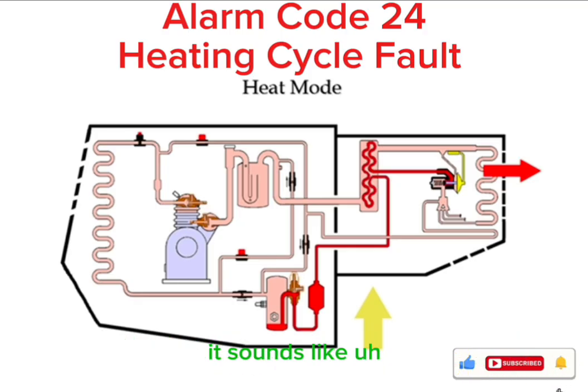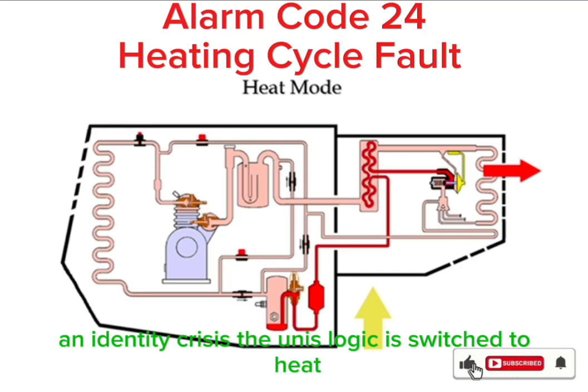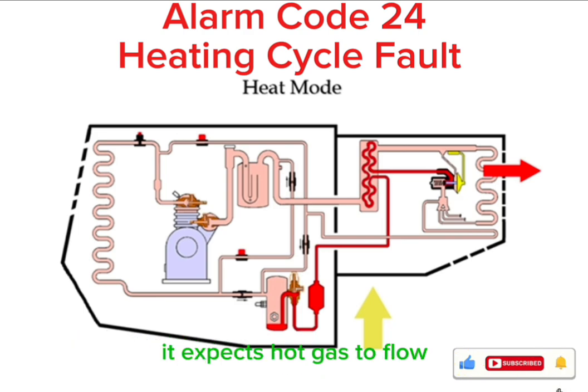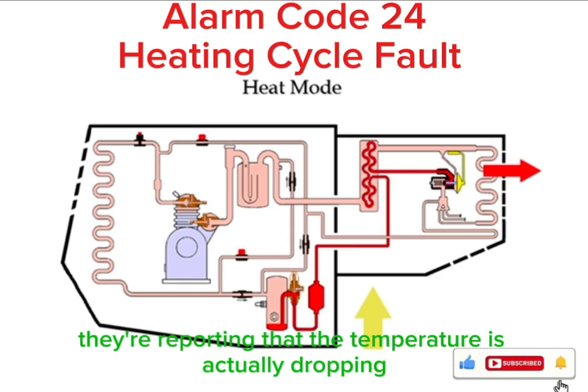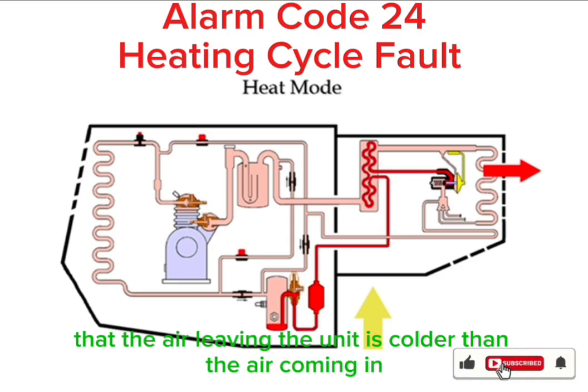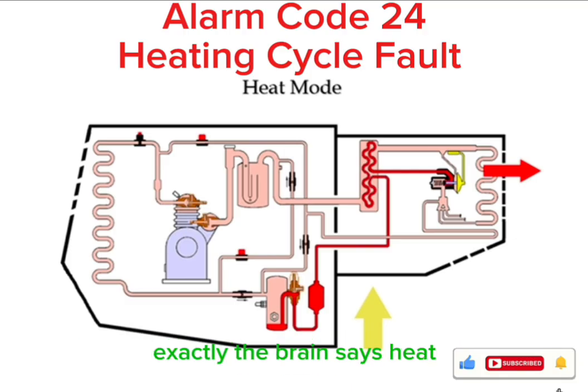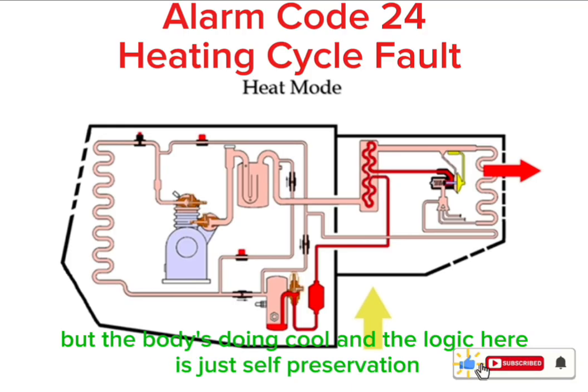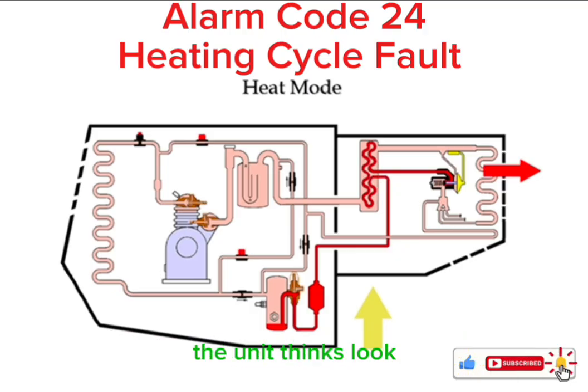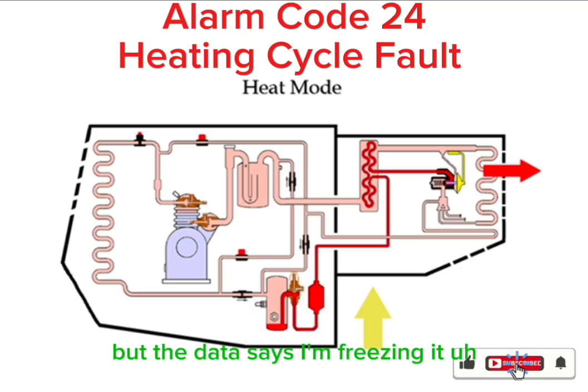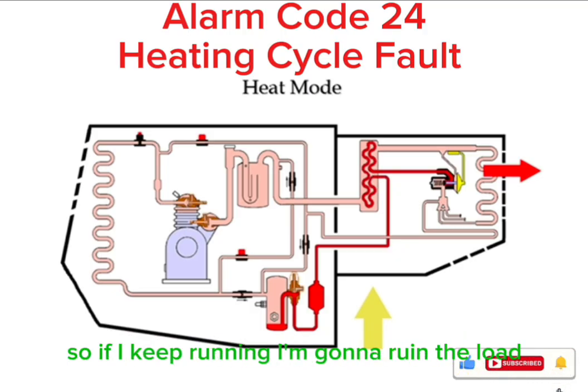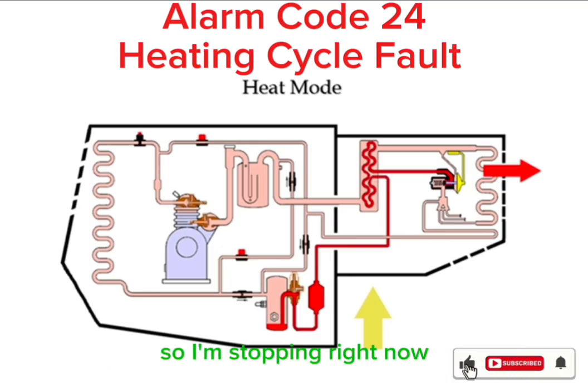It sounds like an identity crisis. The unit's logic is switched to heat. It expects hot gas to flow, but the sensors, the return and discharge sensors, are reporting that the temperature is actually dropping, or at least that the air leaving the unit is colder than the air coming in. Exactly. The brain says heat, but the body's doing cool. And the logic here is just self-preservation. The unit thinks, look, I'm trying to warm this stuff up, but the data says I'm freezing it. So if I keep running, I'm going to ruin the load. So I'm stopping. Right now.